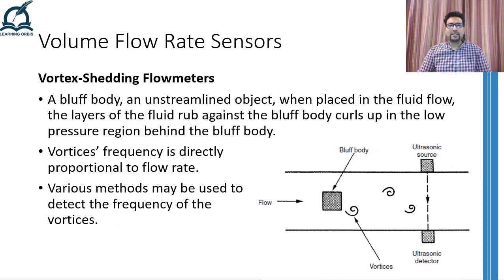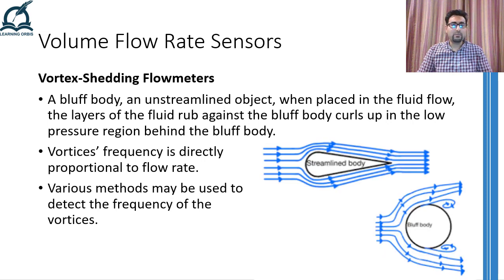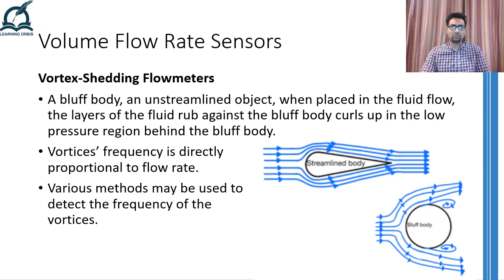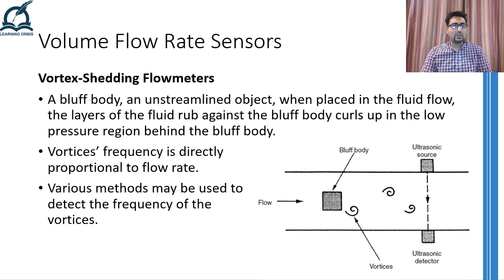The next flow rate sensor is relatively a new one in the lot. It is called a vortex shedding flow meter and it creates an obstruction in the flow of the fluid using an un-streamlined object called a bluff body. The un-streamlined structure causes the fluid flowing past it to rub against the body and slow down. As the layers near the bluff body slow down, they break from the layers which are away from it, and the broken layers curl up and create vortices downstream. The frequency of these vortices being generated is directly proportional to the flow rate.